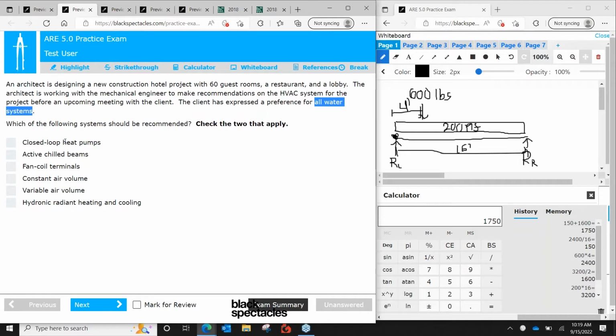So closed loop heat pumps are an all water system. Pipes will circulate chilled water from the chilled water plant in the summer, or heated water from the boiler or other overheated areas like restaurant kitchens in the winter. The heat pumps blow indoor air over the chilled or heated coils. Individual rooms can affect the flow of water to the pipes, regulating the temperature. And while humidity cannot be controlled, this is overall an efficient system. This is actually a good choice for our hotel because it provides both individual control and it is an all-water system. So we're going to check this one for now. We can always come back later if we feel like something else becomes a better option.